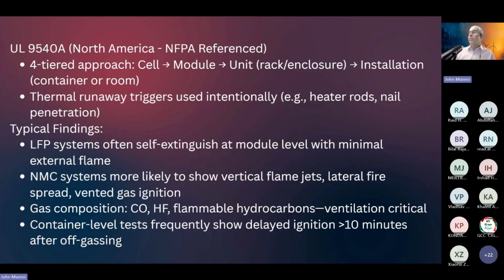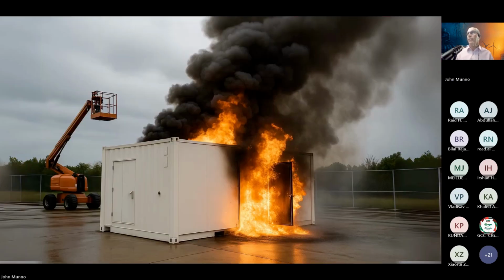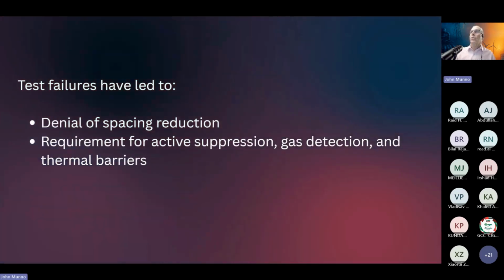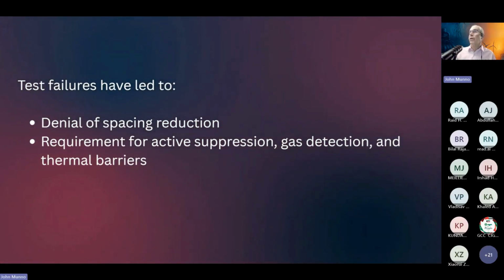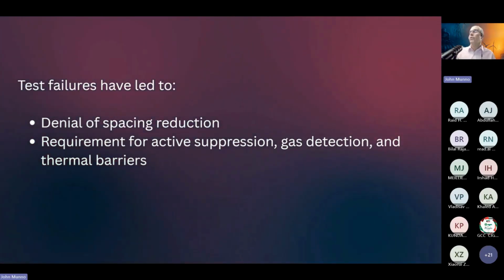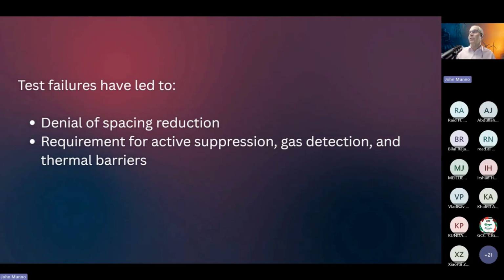Container level tests frequently show delayed ignition. See, that's always a problem. When you don't have immediate ignition of these gases, you build up an explosion potential. So we have to make sure that we don't have a technology that can do that. So when you fail the test, sometimes you are going to have wider spacing, requirements for active suppression, gas detection, thermal barriers, potentially remote monitoring.